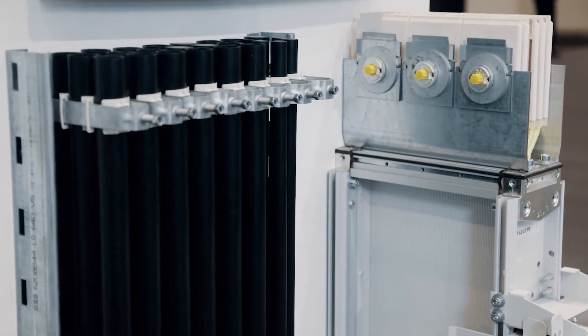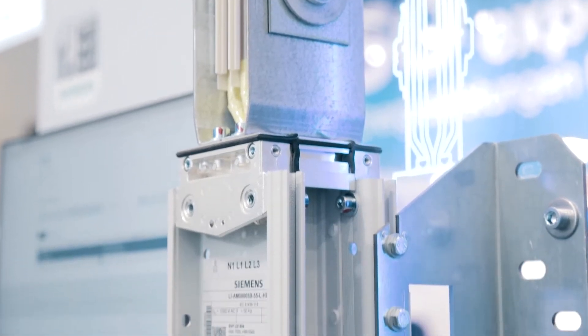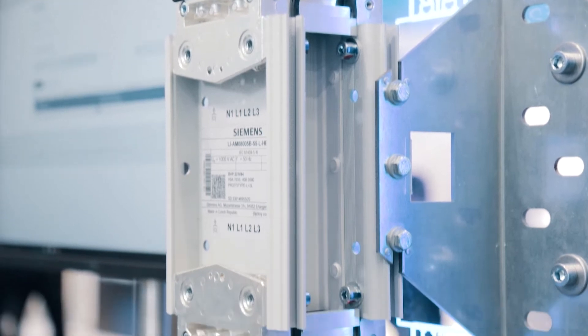Busbar trucking systems are the innovative alternative to cables. To name just a few advantages, the SIVACON 8PS busbar trunking systems are design verified and thus offer a high level of personnel and system safety. And they are more flexible. In case of traditional cable installations, power can only be drawn at defined distribution boards. But in the case of busbar trunking systems, tap-off units can be varied as needed.